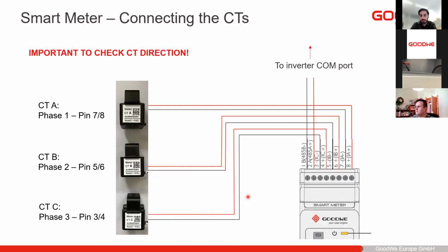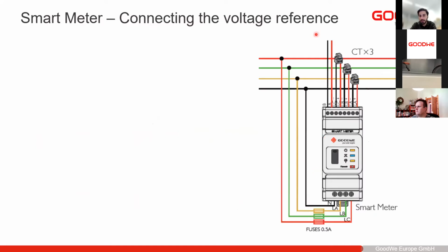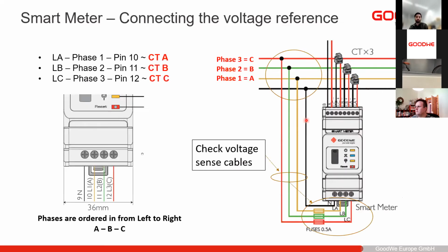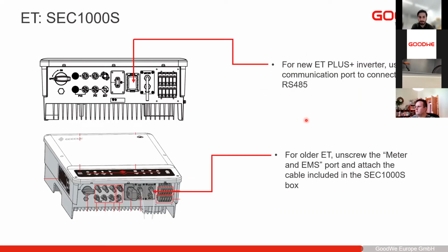Yes. And this is how you connect it. This is also what I showed you. Here on the left side, you have the inverter, and the rest goes to the voltage here. Here you see that the sense for the phases here are reversed for the current sensors as well as the voltage. But it also says on the inverter. Here you see the one I had, the older version of the ET, how it's connected. And here's the newer version.